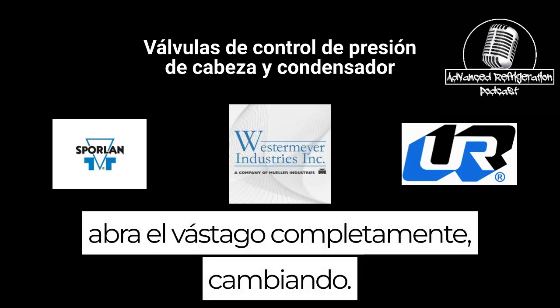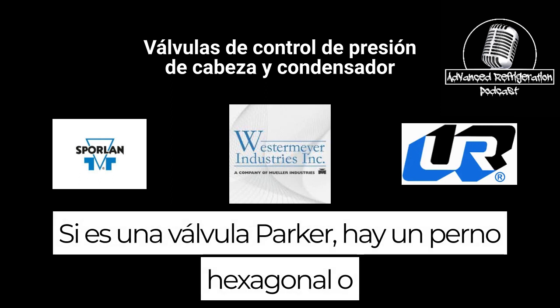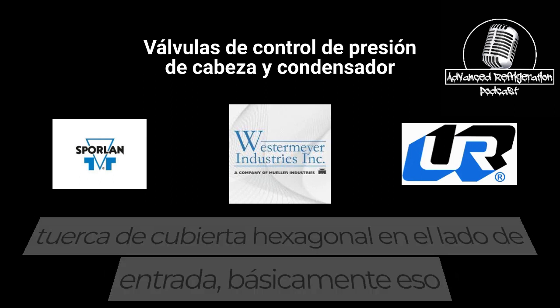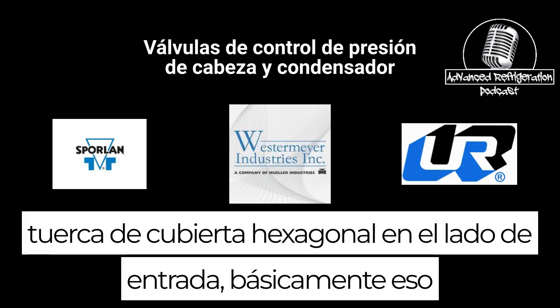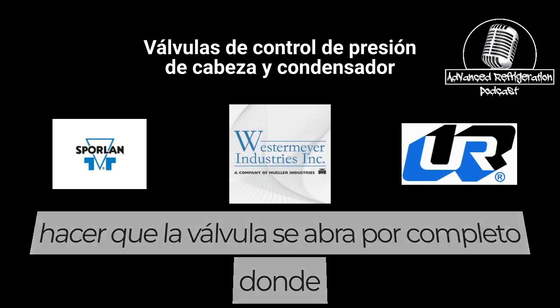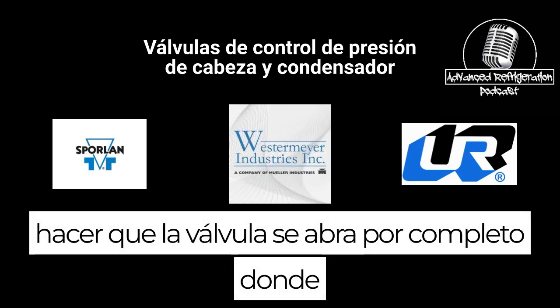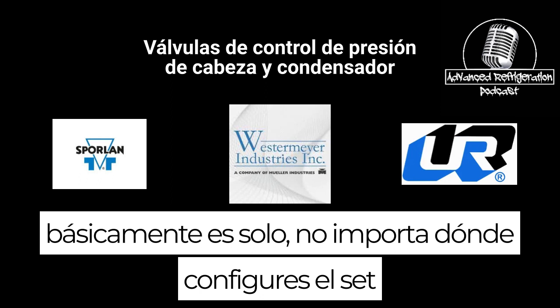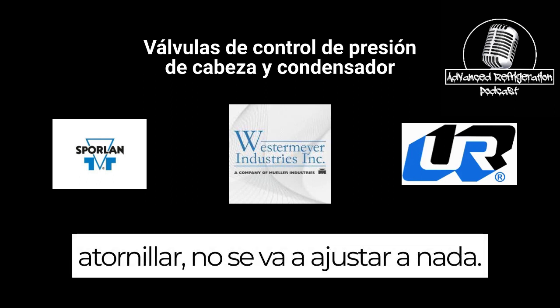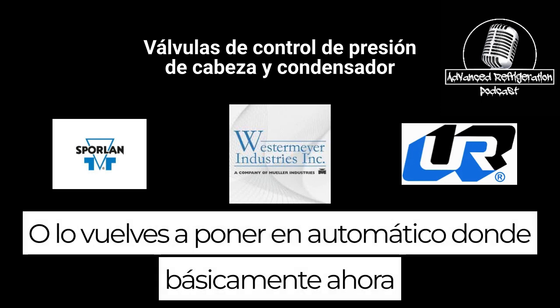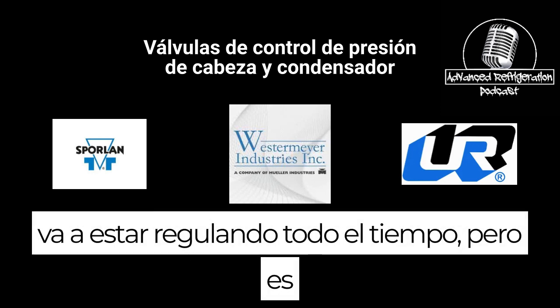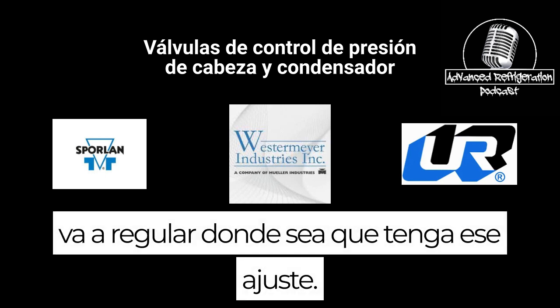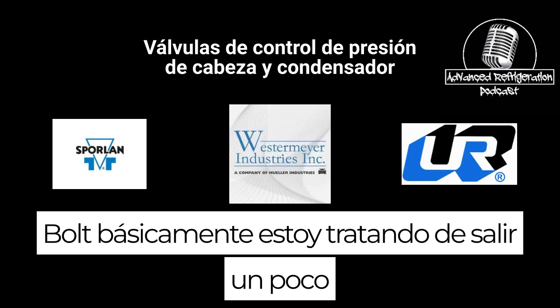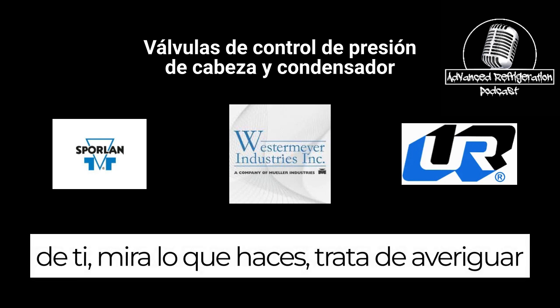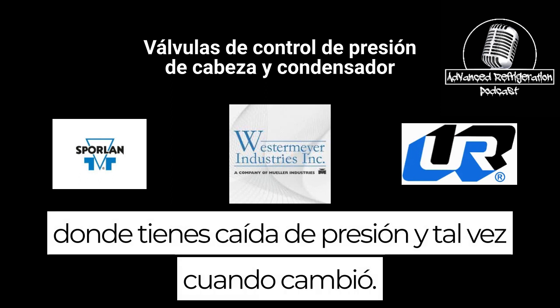So trying to figure out if you have a blocked or sticking valve, besides trying to open the stem all the way: if it's a Parker valve, there's a hex bolt or hex cover nut on the inlet side. Basically that will cause the valve to either go into full open, where no matter where you set the set bolt, it's not going to adjust to anything, or you put it back in auto, where now it's going to be regulating all the time, and it's going to regulate to wherever you have that adjustment bolt. Basically, I'm trying to get a little bit out of you to see what you do to try to figure out where you have pressure drop and maybe why and when to change.